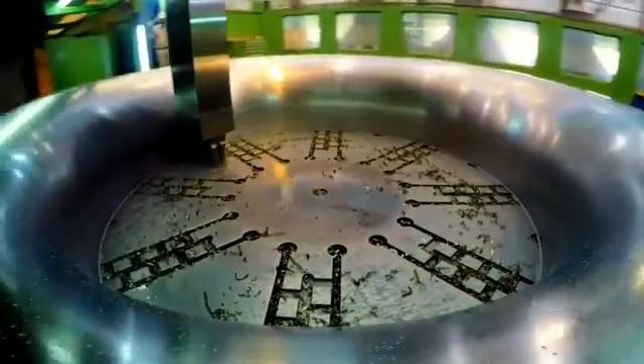The only thought that came to my mind is that the size is quite large, because earlier we have done lift irrigation pumps having capacity of around 30 megawatts or so, but this time around the call was different. The motor along with the pump that was required to be designed was of the order of 139 megawatts. So that was quite a jump.